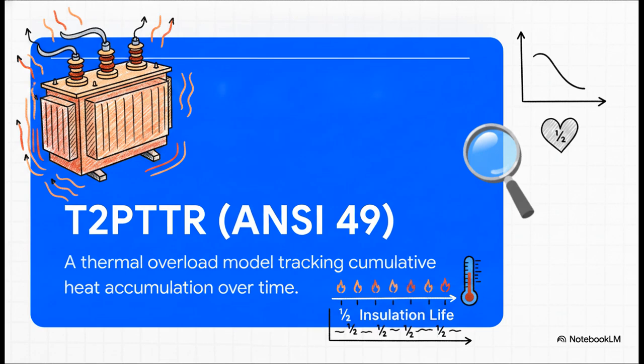Let's break down that thermal layer. So while the differential stage catches the sudden, violent faults, the T2-PTTR thermal model, or ANSI 49, is more like an athlete's heart rate recovery monitor. It tracks the slow-building, cumulative heat stress over time. This is super important because every single time the sustained hotspot temperature rises just 6 to 8 degrees Celsius above its rating, it roughly cuts the expected lifespan of the transformer's insulation right in half. So this model constantly tracks how much heat builds up and cools down to prevent long-term, irreversible aging.